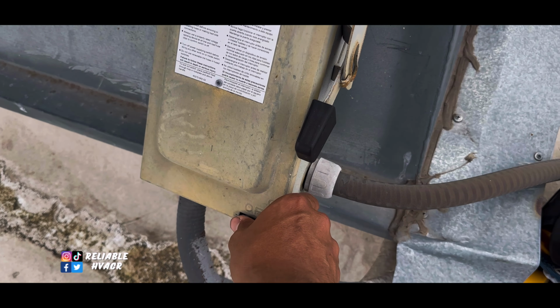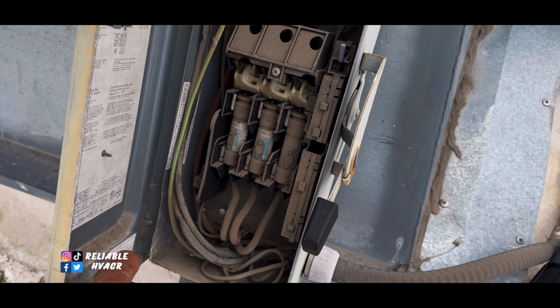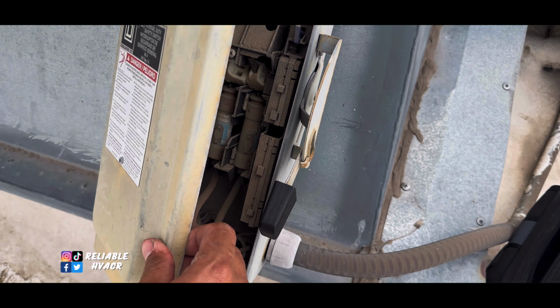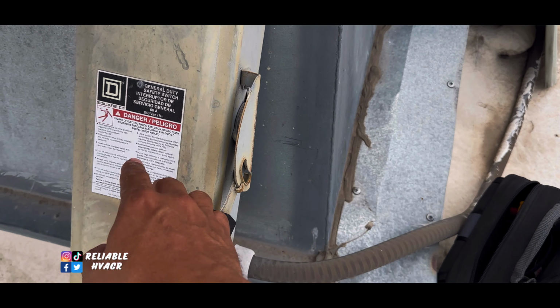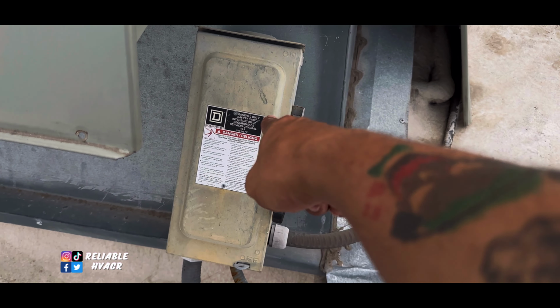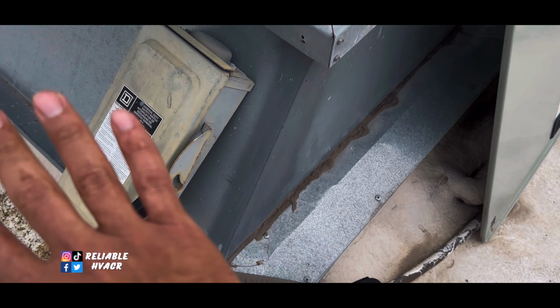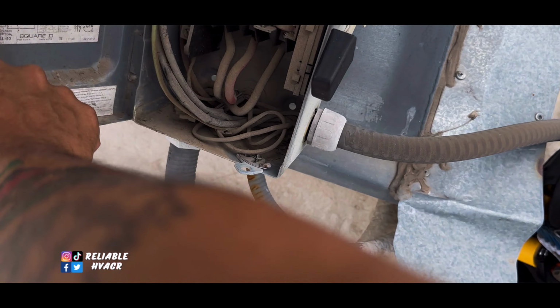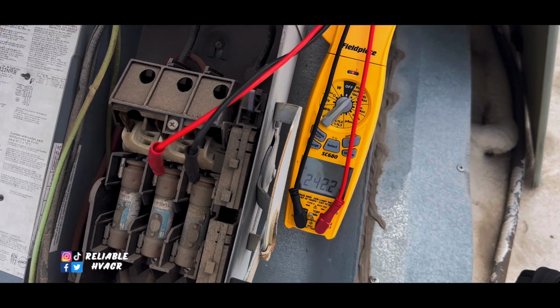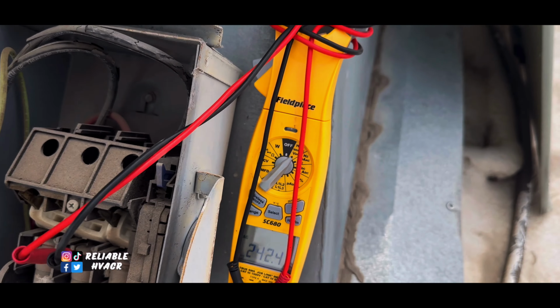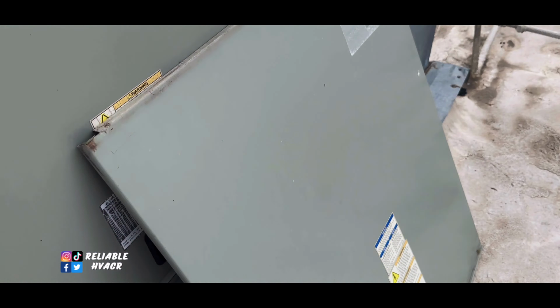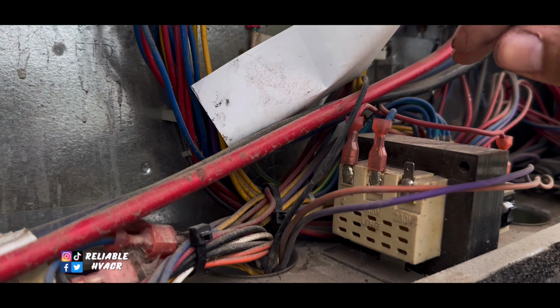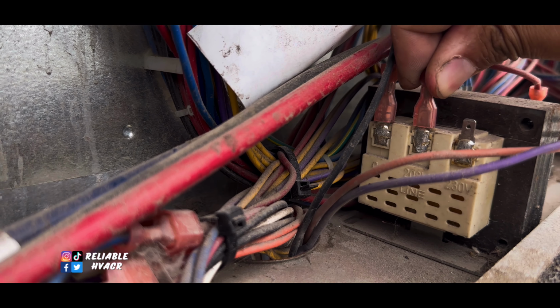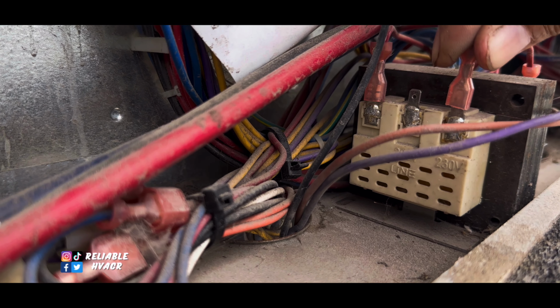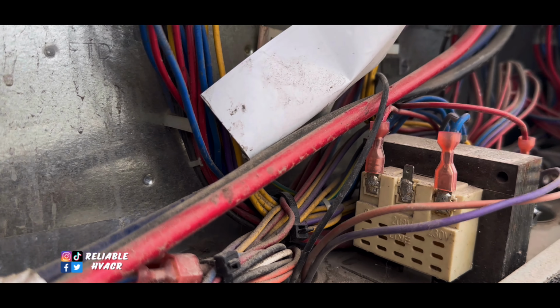All right, so we turn off power. I'm getting this confused with another location. This one's still intact. There was one that was burnt up and it was pending a new disconnect. So like I said, new unit, I'm pretty sure that was reused. So we've cut off power, and let's make sure our voltage is fine here. So we have about 240 across all of them. Man, I haven't worked on this in forever, but I guess I had missed this. Somebody put 208 and we needed 230.